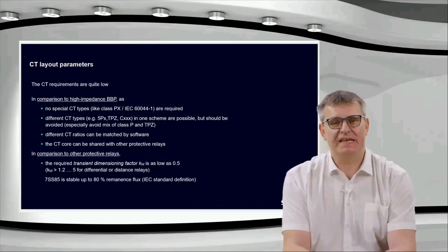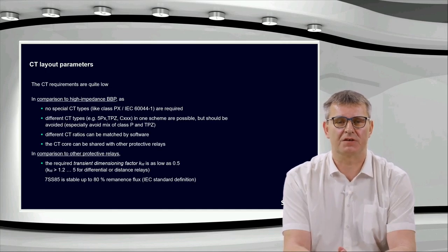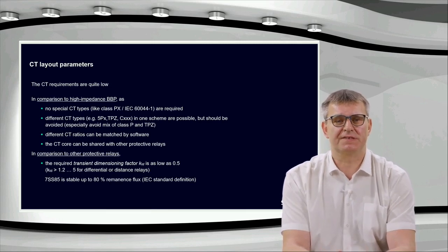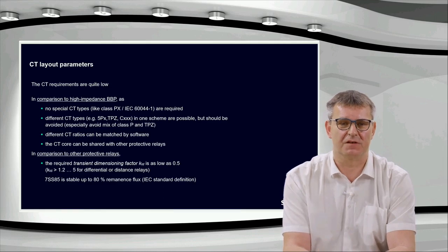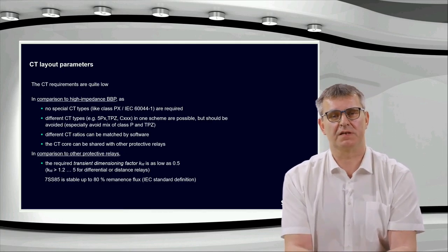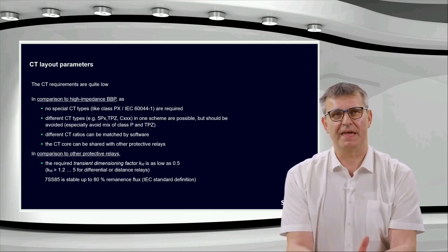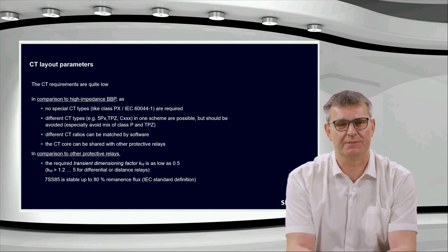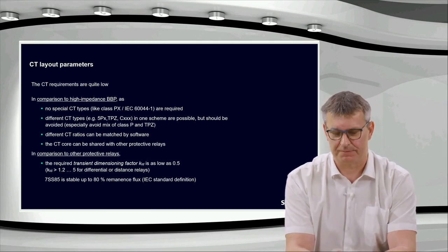Very important to state that the 7SS85 is stable, and this is proved also via a KEMA certificate for a remanence of up to 80%. The calculation I will do is assuming that the remanence will be below 80%. If the remanence is higher, we will soon introduce corrections in our manual to make the CT core requirement a little bit higher, to also deal with a remanence of more than 80%. But for today, I will assume a remanence of up to 80% only.